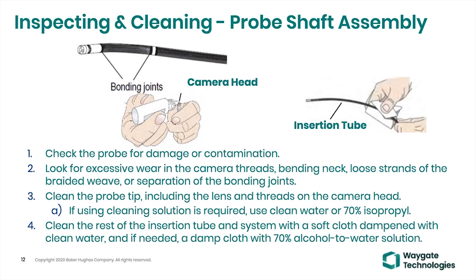And make sure when you're wiping that down, like the hand is showing in the right-hand side, feel for any kinds of kinks or dents or any kind of anomalies, and have a discussion with your coworker or your manager to point it out and determine, this is the analogy, do I need to change the oil? In other words, do I need to do some preventive maintenance before it gets worse?